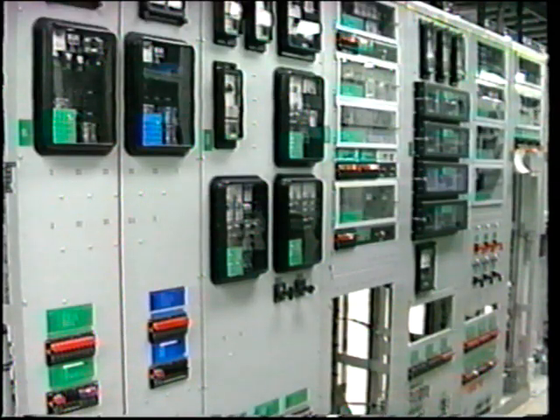But these relays were not part of the test. They had probably been in this condition for some period of time. Additional wiring had been added some time ago, and this prevented the cover from being replaced at that time. Clearly, special covers should have been made to fit the new situation. Relays should always have covers in place when in operation. Apart from the possibility of inadvertent operation, there is the likelihood of dirt and moisture getting into the relay components.